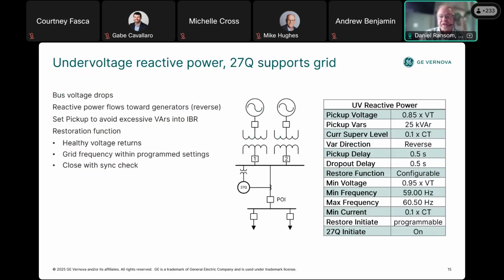The 27Q element shown here does that. If a voltage drops and an inductive reactive power flow in the direction towards the generating unit, that's reverse, is detected, then the network connection point needs to have something happen there to take off the generation system, to disconnect it, be CB1 or CB2. When the element's set to reverse under normal conditions, the power flow can be either way, but what's important is that the VARs are flowing into the IBR system. So protection will trip if the reverse reactive power measurement is positive in the reverse direction and exceeds the programmed pickup VARs level and direction. There's a restoration function that'll keep it going and get it sync checked as it comes back online automatically.